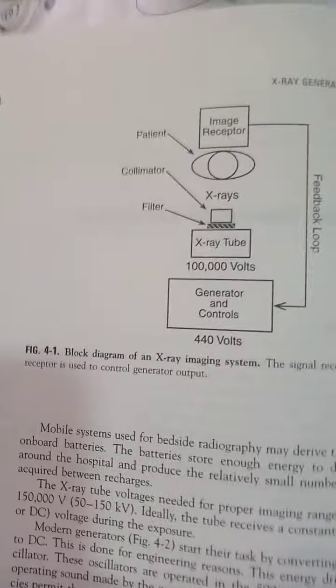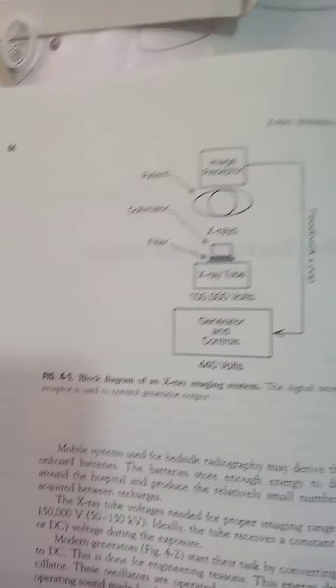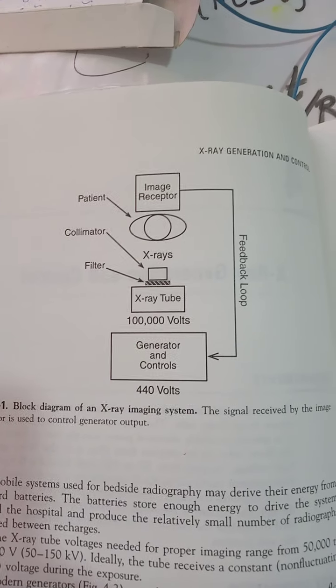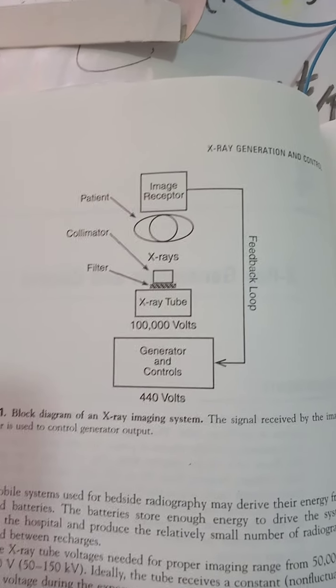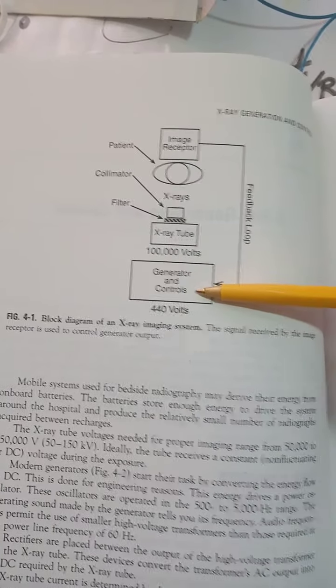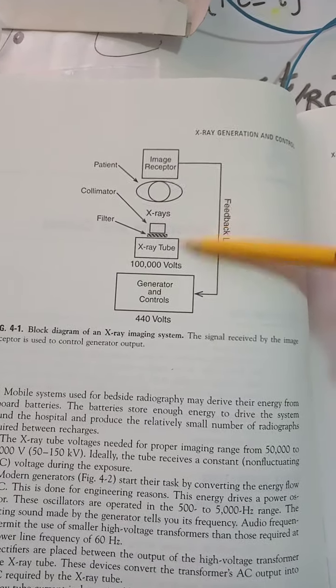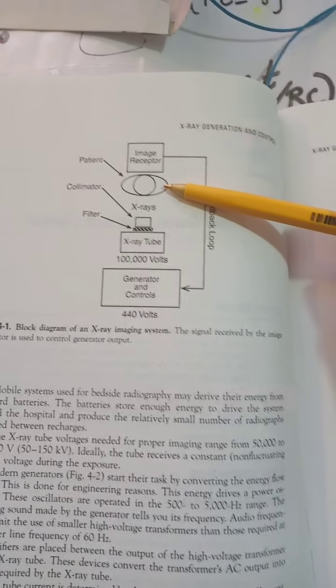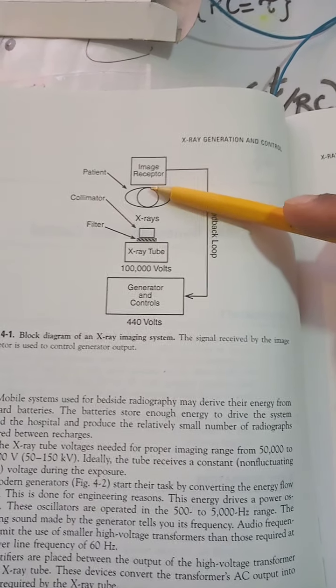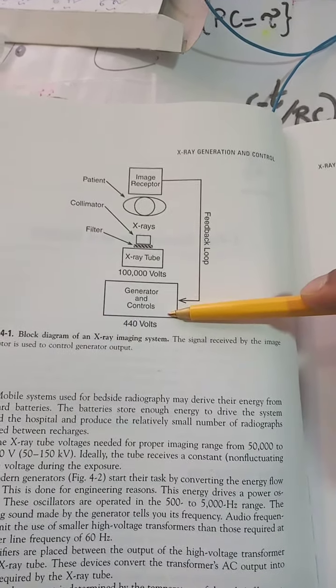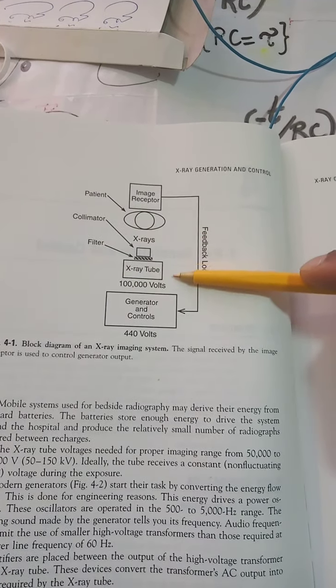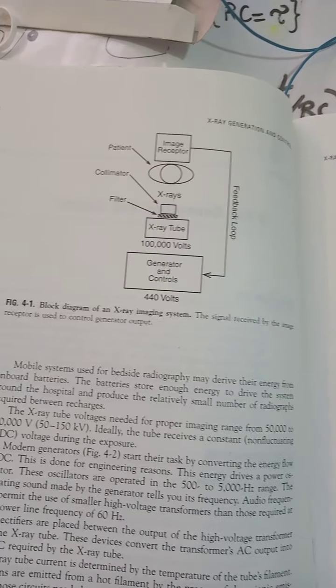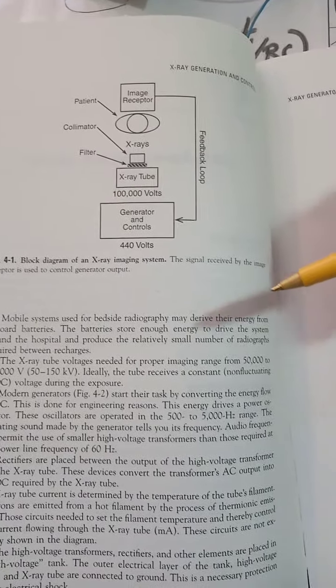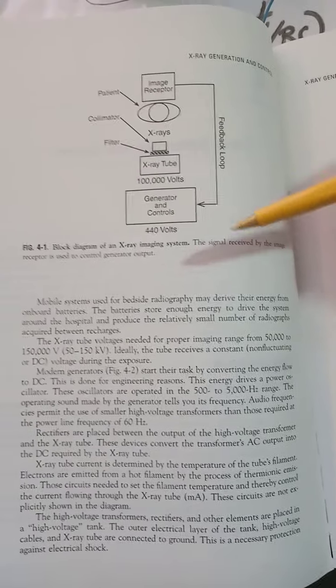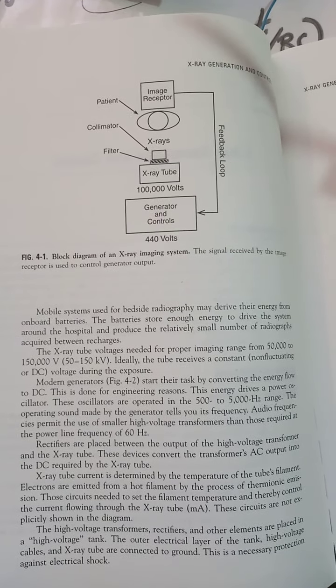So the block diagram of an X-ray imaging system is shown through an algorithmic diagram. So you've got the generator, which is the transformer taken in, and then the X-ray tube, the X-ray gun, and then the X-ray is being produced here. The patient is lying down here, and then the image receptor is recording everything, and then sending it back to the feedback loop to moderate and modulate the amount of radiation being pushed out of the generator into the X-ray tube, and by the X-ray tube onto the patient.